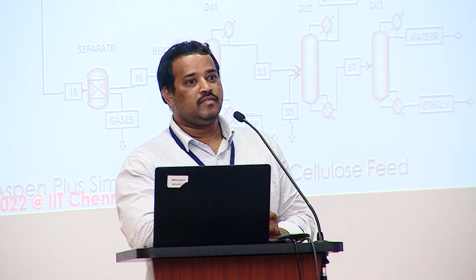Okay. If we are using the condensate or the cooling water from the condenser, the normal practice is that we are not really seeing the cooling water coming out from the condenser in vapor condition. So there is a reason I'm curious about. Yeah, we are using the condenser cooling water, and the heat you are extracting from the stream, you are not using. We are sending that water to the cooling tower to regenerate the process stream. So the heat which you are wasting to that cooling water can be recovered with the help of this technique. Hope it's clear.